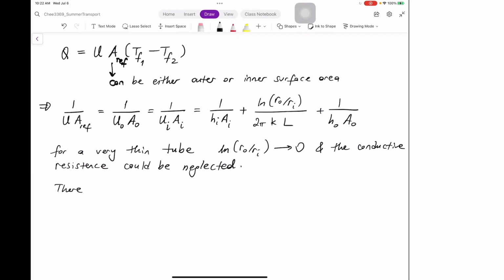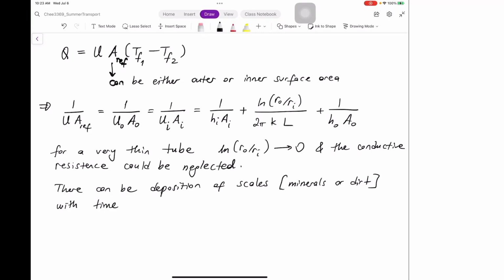So there can be deposition of scales, minerals, or dirt with time. Or they can simply get rusted, and the conductivity can change, because metals are good conductors, but when they rust they become poor conductors. In the heat exchanger, this adds to the heat transfer resistance.